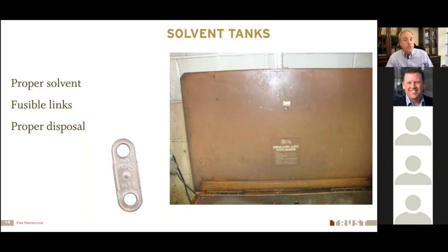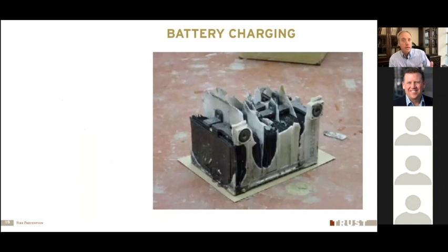If you are using a flammable solvent in your parts washer, make sure that parts washer has a fusible link on there, which is a device that's attached to the lid of the parts washer, where if you get a fire inside the parts washer, that link will melt and let the lid drop closed over the fire, smothering the fire. So be very careful with that equipment, because those often do present a lot of flammable material into your work environment, especially in a way where they could catch on fire.